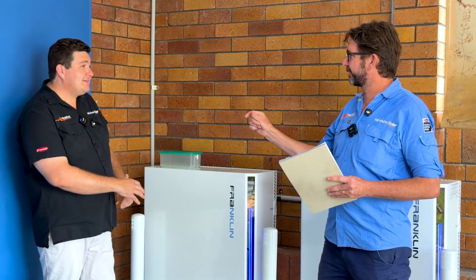They do give you a really nice trolley — they lent us a trolley for our first install, and apparently you can manually handle it off the back of the truck. Just make sure you work it out at the warehouse before you arrive on site. I wouldn't be doing it on site, especially with a high truck bed. Use a forklift for the first time. The install overall was really smooth and pretty easy. Alan did an excellent job and was very meticulous with it, except there was one little line in the install manual: 'Make sure you put a neutral link between the neutral from off-grid and the neutral from on-grid.' He missed this one little line, which was really annoying. Franklin was supposed to be on site on the day to help talk through it, but they kept changing the days. What they want is to link the off-grid neutral and the on-grid neutral together — why they don't do that from the factory, I don't know. But even if you don't, just put a neutral link in the box with a big label saying 'don't forget.' A little bit frustrating, but no big deal — apparently it happens all the time.